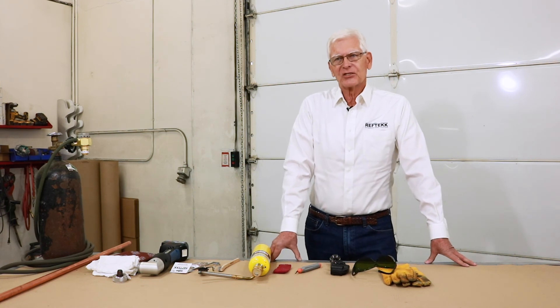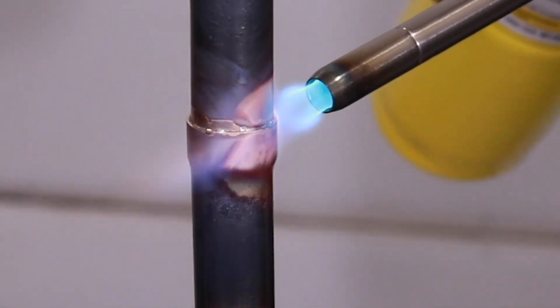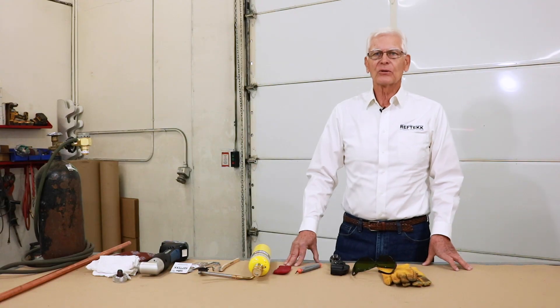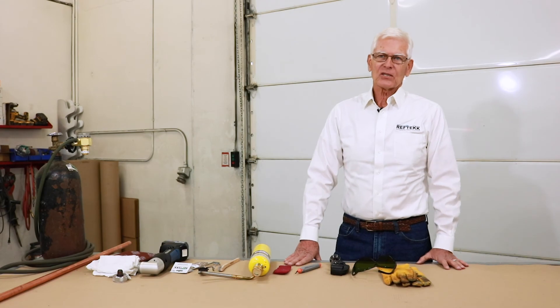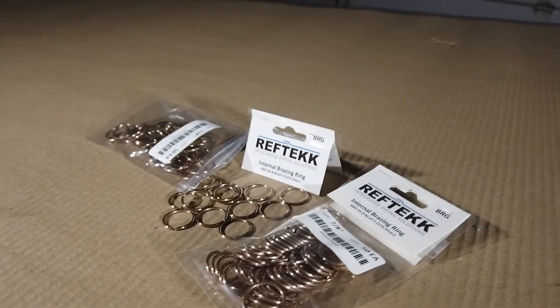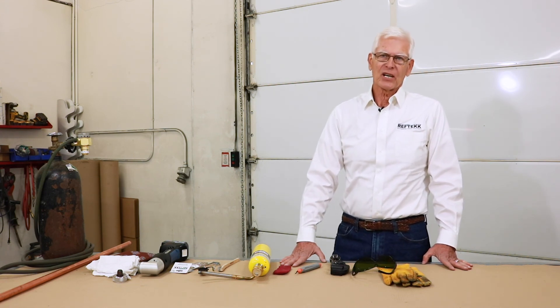The next cool thing is the brazing ring. This allows you to braze the joint from the inside out, creating a fillet on both ends of the joint — one on the inside and one on the outside. This means you have a full-depth braze, giving you the best chance for a leak-free brazed joint. Reftekk brazing rings are BCuP-5, meaning copper phosphorus with 15% silver — self-fluxing on copper, similar to Silphos 15 or Stay-Silv 15. There are different ring sizes for each tube size and they contain enough brazing filler to complete even a solder-depth socket from store-bought fittings.